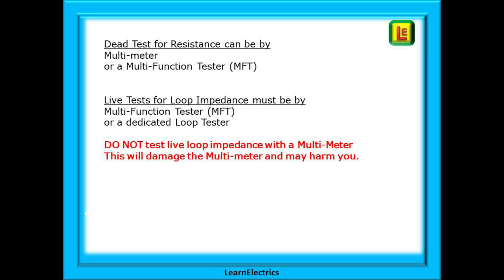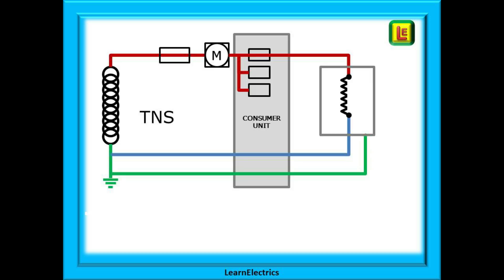We can begin with the reminder of the three types of earthing system in popular use. This system shown here is TNS. The earth and neutral are in separate conductors throughout the whole system. There is the more modern TNCS system where the earth and neutral are combined in the same cable up to the property and at the point of entry to the building they are separated into an earth and a neutral conductor.